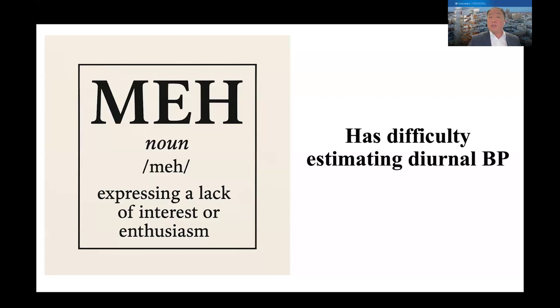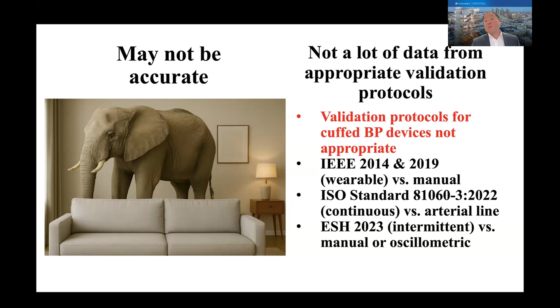And then finally, the elephant in the room: are they actually accurate? Believe it or not, the ruler that we use to determine whether a device is accurate has only recently been standardized. It's not appropriate to use old-fashioned protocols that are based on cuff devices. We do have the IEEE 2014-2019 standard, which was published, but not many studies used it. More recently, we have ISO standards for continuous blood pressure measurement, and in 2023 ESH published a protocol. Not a lot of devices have actually been validated using those more modern protocols. So the question remains: are these devices accurate?